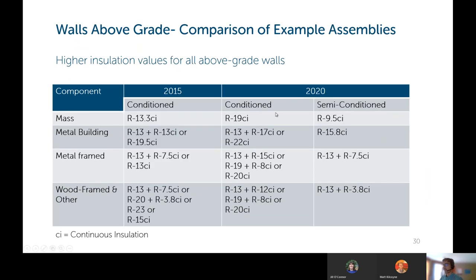So how this has changed from 2015, as I mentioned, it's higher insulation values for 2020 than it was for 2015. So if you're comparing some example R values, a mass wall has gone from R13.3 continuous to R19 continuous. Metal buildings have increased somewhat. All of them have across the board. Wood framed walls, you could have done R15 continuous in 2015. Now R20 continuous will be required for conditioned spaces.